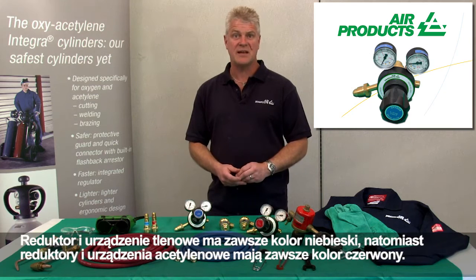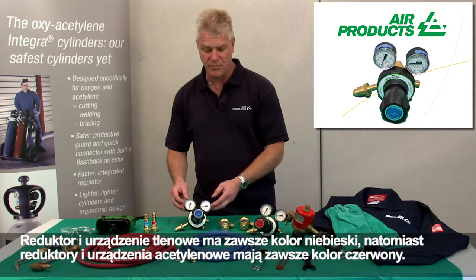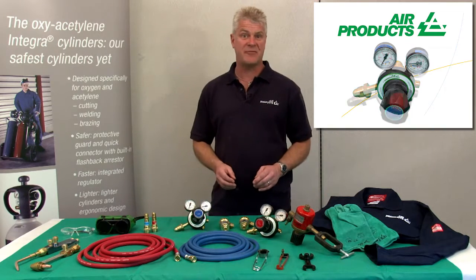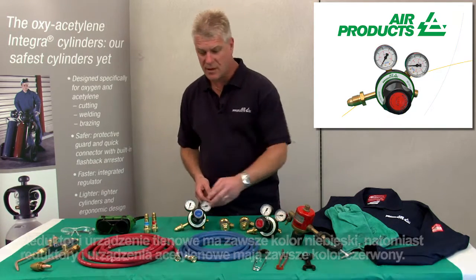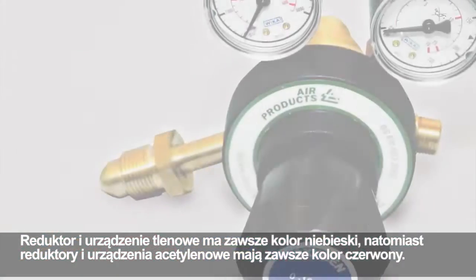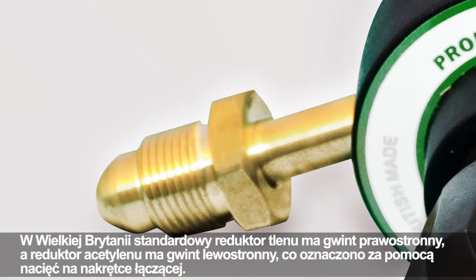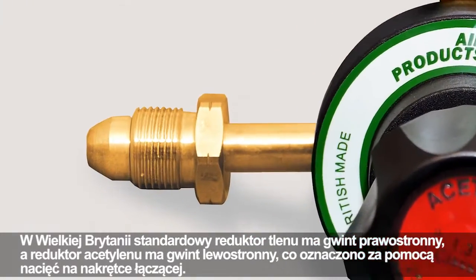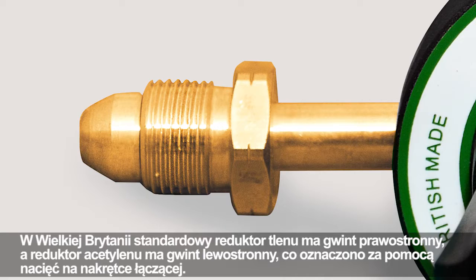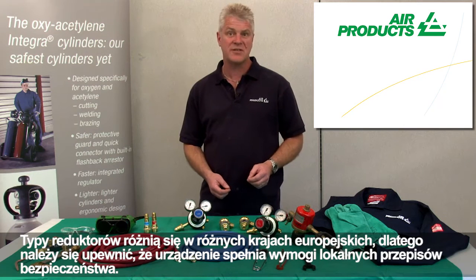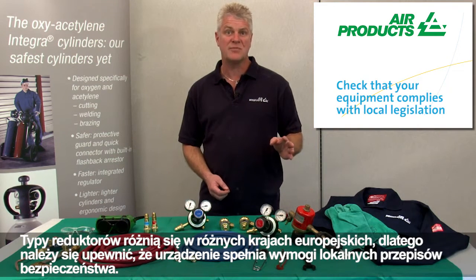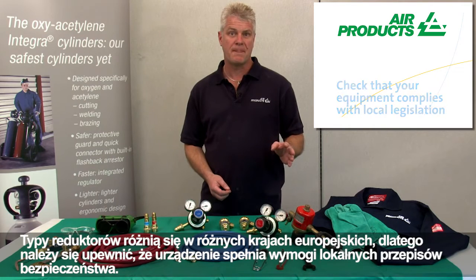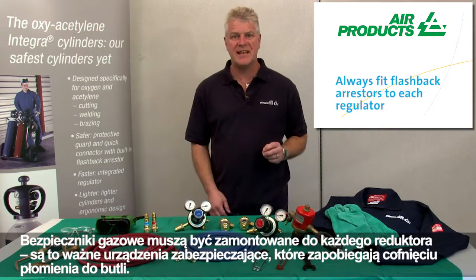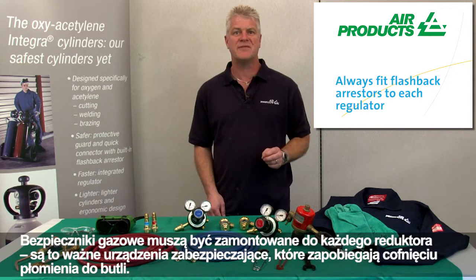An oxygen regulator and equipment is always blue. Acetylene regulators and equipment is always red. A standard oxygen regulator has a right-hand thread and the acetylene regulator has a left-hand thread in the UK, identified by the notches in the connecting nut. Regulator types vary between European countries, so please ensure your equipment complies with local safety legislation. Flashback arresters must be fitted to each of the regulators. These are important safety devices designed to prevent flames returning into the cylinders.